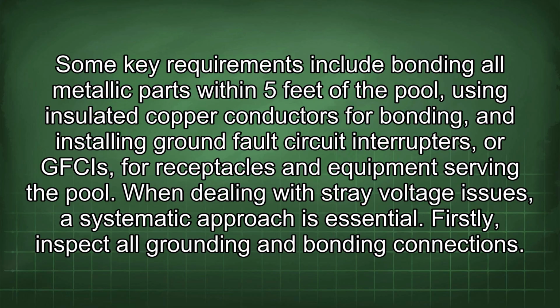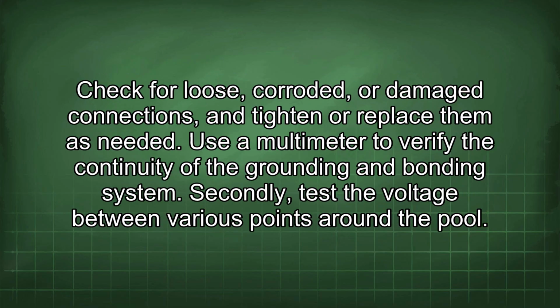Firstly, inspect all grounding and bonding connections. Check for loose, corroded, or damaged connections and tighten or replace them as needed. Use a multimeter to verify the continuity of the grounding and bonding system.